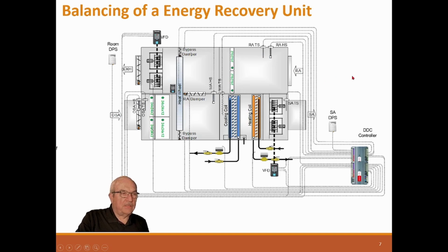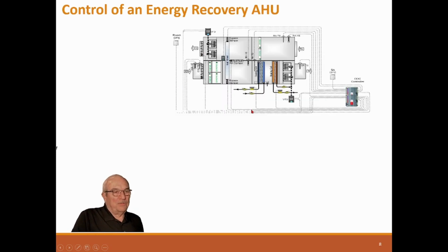So this is basically about, and these can be quite large. I've done several of them that are 20 or 30,000 CFM. And this is just a simple sequence for this unit. I did one set of units for a big civic center that had 11 loops in an air handler. I've never seen an air handler like it. If you look at this, it basically has 1, 2, 3, 4 loops. Maybe 5 loops in the wheel. So that one had 11 loops. You can't imagine how complex that engineer made that job. So it is possible to be complicated on this.